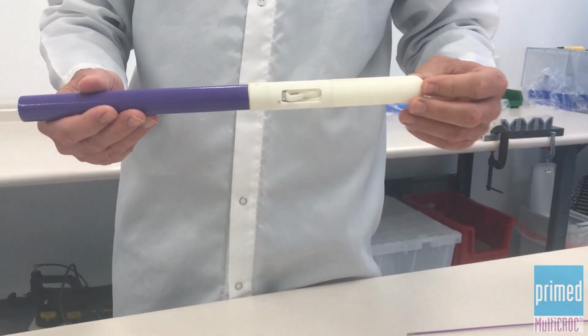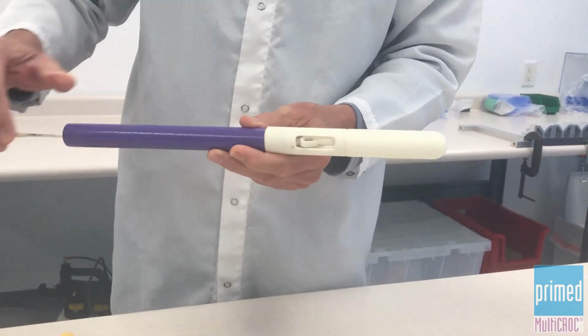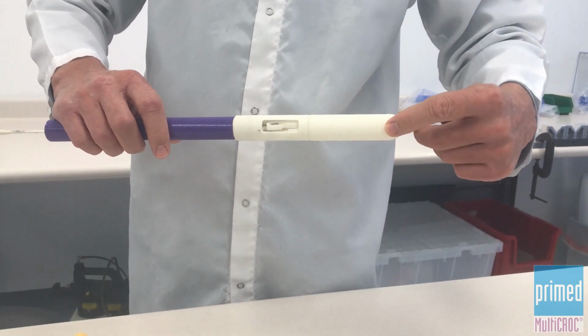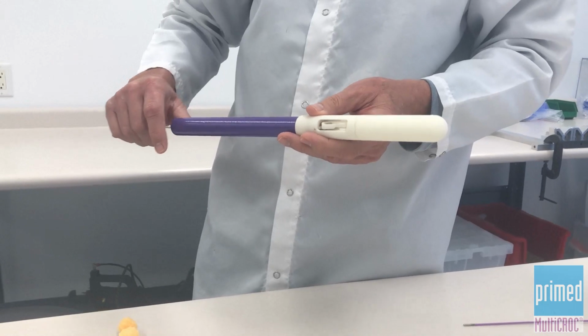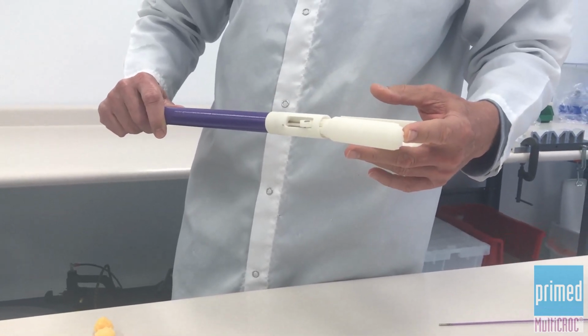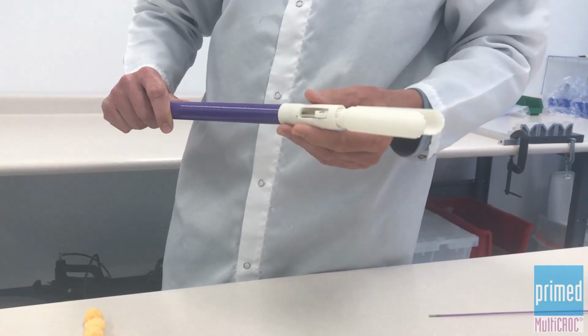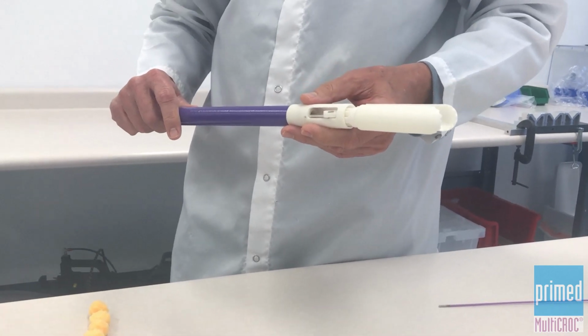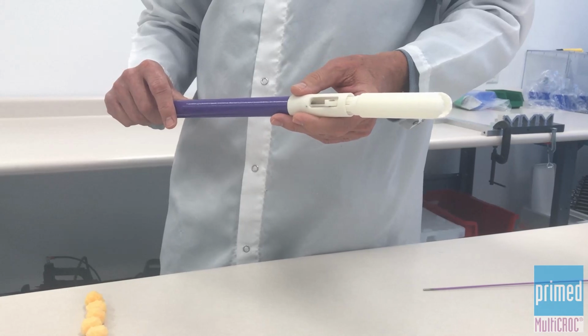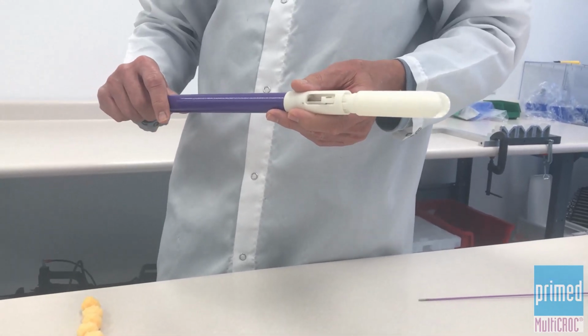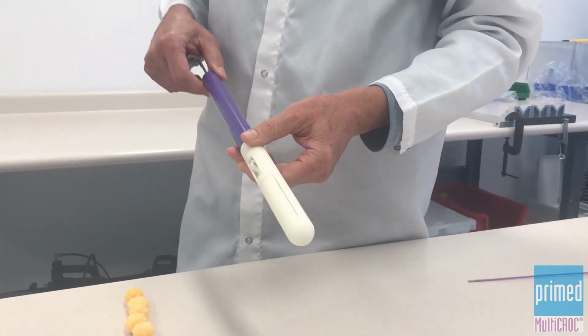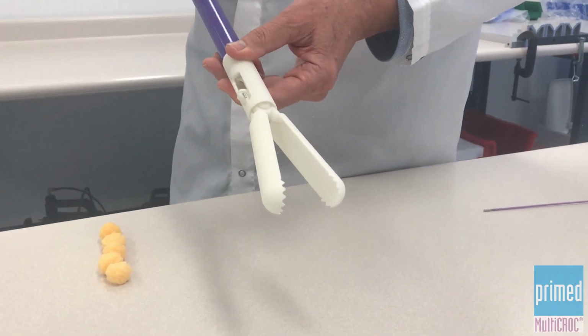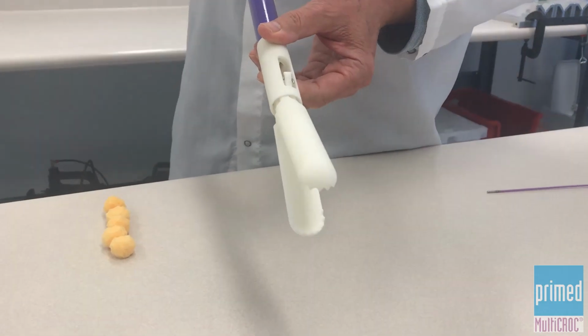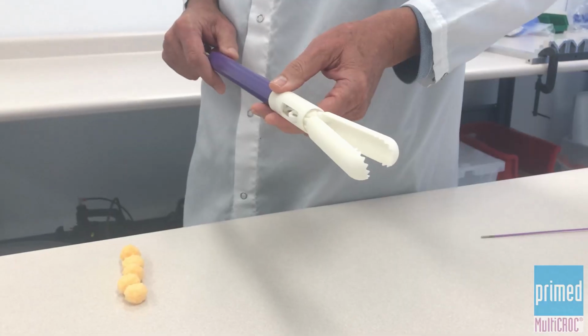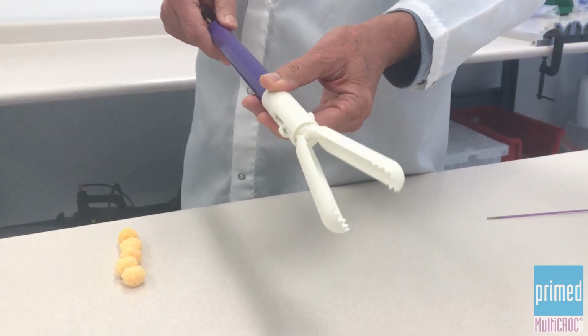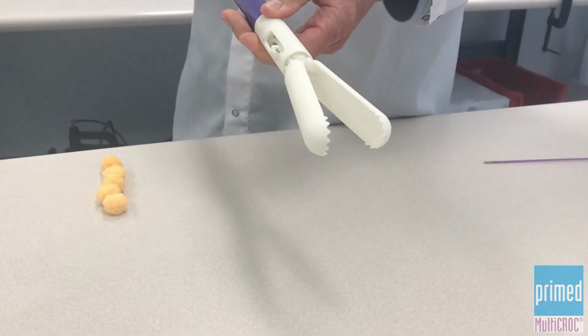By moving the jaws back into the ferrule, we exert a very high clamping force in this area that is transmitted into the clamping force at the tips of the jaws, those tips, by the actual tissue. In fact, as measured, the clamping force at the end of the jaws of the MultiCROC is about 35% higher than the clamping force of the Boston Scientific Jaws 4 biopsy forceps. The back movement of the jaws into this housing is virtually unnoticeable to the user. Sometimes first-time users, depending on the actual orientation of the device, may have difficulty realizing whether the jaws are open or closed. If we look like this, it may appear that they are not open. It is just a matter of getting used to the device, and the learning curve is very short. And the user immediately understands and knows whether the device is open or not.